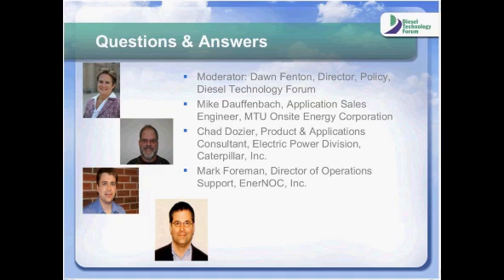Well, I guess I'll start with that one. The biggest thing you'll run into as you move into some of the newer tiered engines, specifically with biodiesel, is to ensure that you maintain the same standard of fuel quality that diesel needs. One of the things with Tier 4 regulations is we're moving to ultra-low sulfur fuel, so if you're going to consider using biodiesel, you need to ensure it's mixed with that ultra-low sulfur fuel. For mixes, refer to your engine manufacturer, but typically we see B20 is not a concern for most Tier 4 product.